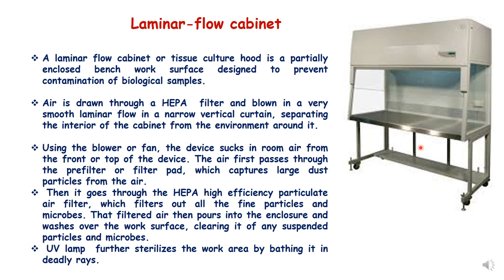Using a blower or fan, the device sucks in room air from the front or top. The air first passes through a pre-filter or filter pad, which captures large dust particles, then through the HEPA filter, which filters out fine particles and microbes. The filtered air then flows into the enclosure and washes over the work surface, clearing it of suspended particles and microbes. A UV lamp is also present in the laminar flow cabinet, which further sterilizes the work area by killing microbes on exposure to UV rays.